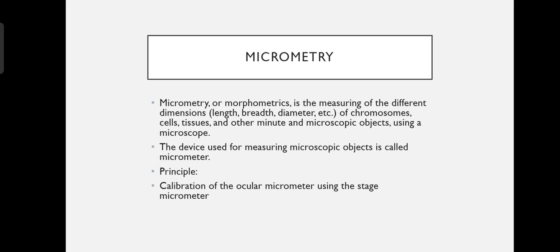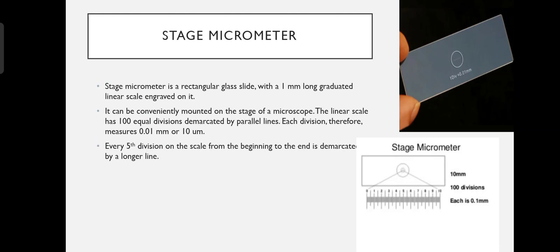Since microorganisms, cells, and such minute objects are visible only under a microscope, a suitable scale for measuring them should be within the scale itself. The device used for measuring microscopic objects is called a micrometer. A micrometer consists of two components, namely stage micrometer or objective micrometer and ocular micrometer or eyepiece micrometer. Stage micrometer is a rectangular glass slide with a 1 mm long graduated line scale engraved on it.